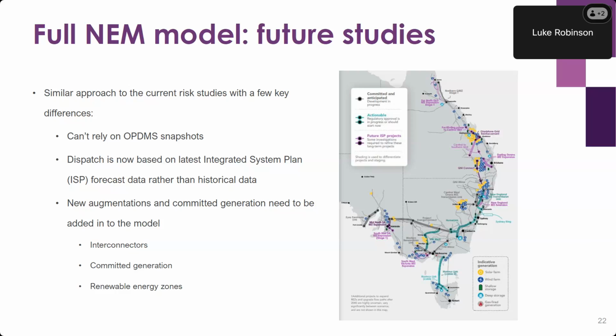Based on the risk that we're studying, we'll choose data that aligns with the risk conditions, such as if we want to look at high or low NEM demand. We might be looking at low synchronous generation dispatch if we're studying a minimum system strength risk. We might look at cases with high solar, high rooftop solar online, things like this.